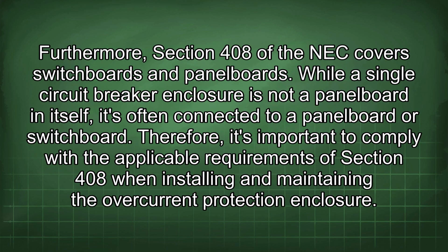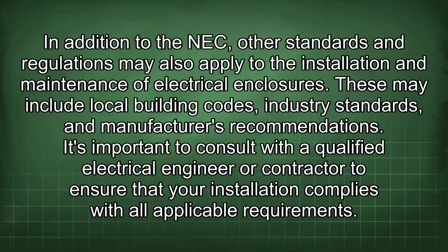Section 408 of the NEC covers switchboards and panel boards. While a single circuit breaker enclosure is not a panel board in itself, it's often connected to a panel board or switchboard. Therefore, it's important to comply with the applicable requirements of Section 408 when installing and maintaining the overcurrent protection enclosure.